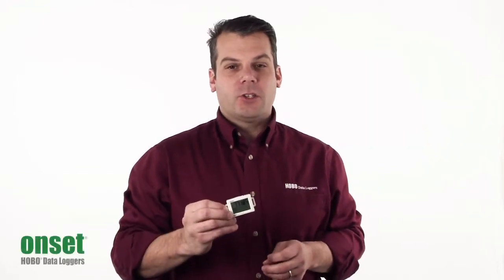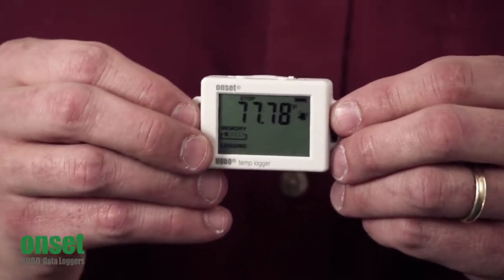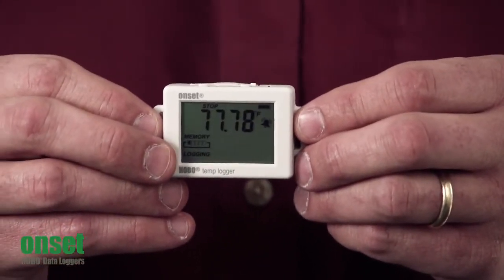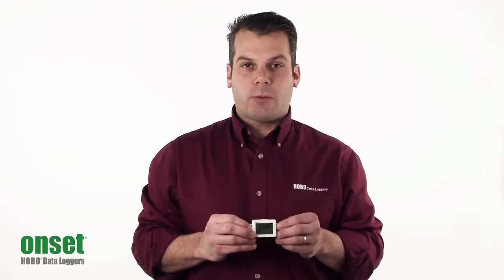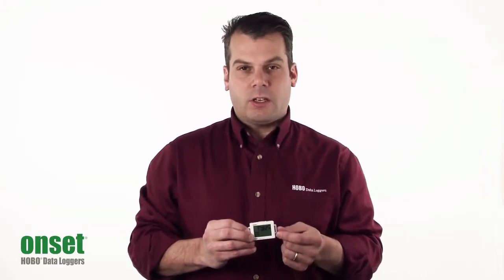and today we're going to take a look at the UX100 HoboTemp. This is part number UX100-001. It has an accuracy of plus or minus 0.4 degrees Fahrenheit or 0.2 degrees centigrade, and it has the capability of storing 84,000 measurements. Some of the key features include the LCD.